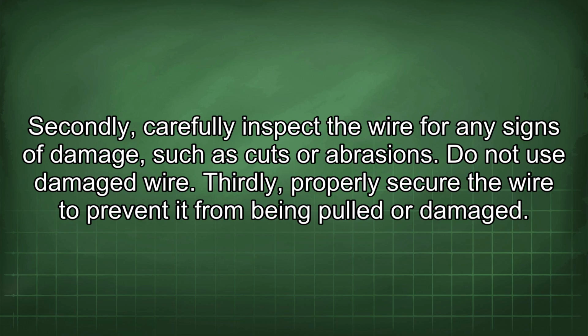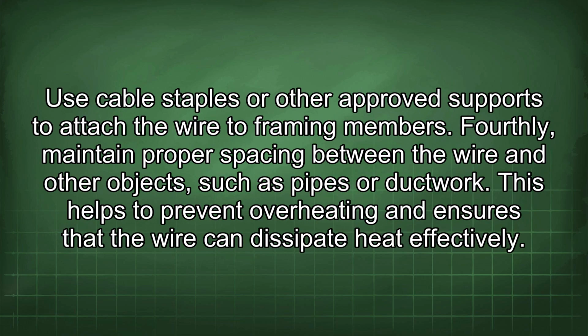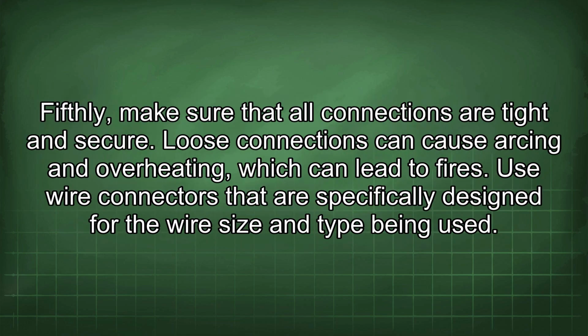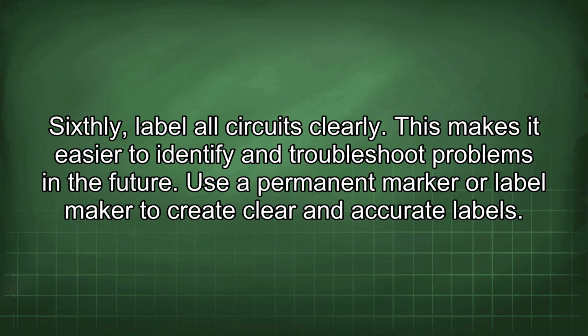Thirdly, properly secure the wire to prevent it from being pulled or damaged. Use cable staples or other approved supports to attach the wire to framing members. Fourthly, maintain proper spacing between the wire and other objects such as pipes or ductwork. This helps to prevent overheating and ensures that the wire can dissipate heat effectively. Fifthly, make sure that all connections are tight and secure. Loose connections can cause arcing and overheating, which can lead to fires. Use wire connectors that are specifically designed for the wire size and type being used. Sixthly, label all circuits clearly. This makes it easier to identify and troubleshoot problems in the future. Use a permanent marker or a label maker to create clear and accurate labels.